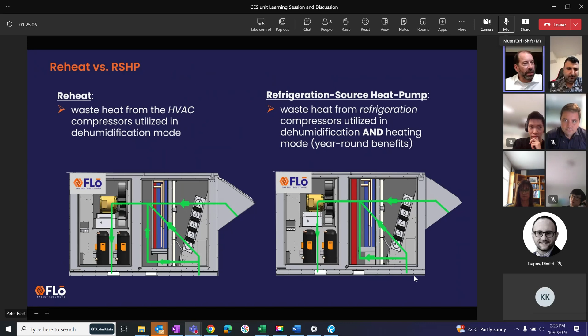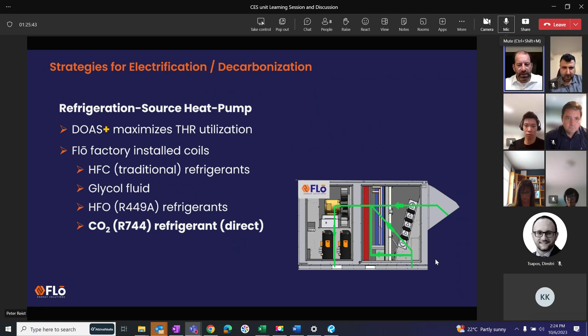All right, so some of the strategies: our approach maximizes that utilization. We factory install those coils, and we can do HFC, synthetic refrigerants, and glycol fluid, and we're talking about HFOs and CO2, CO2 being the very best refrigerant for this. Just to give you a sense, some of the temperatures we get out of, say, R-449 refrigerant on a reclaim, we probably get around 160 degrees Fahrenheit. With CO2, we're well into the 200 degrees Fahrenheit realm. So really, really high quality heat that we get from CO2 racks. It's really great that almost everybody in Canada does CO2 refrigeration. It's a big benefit.